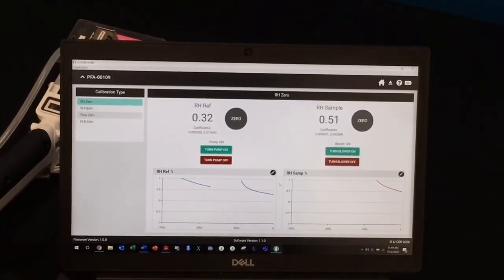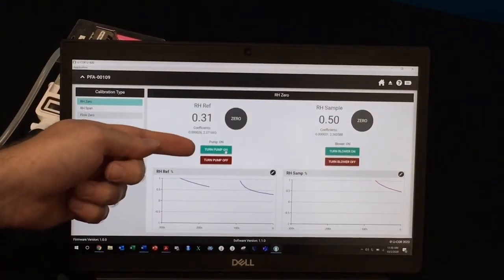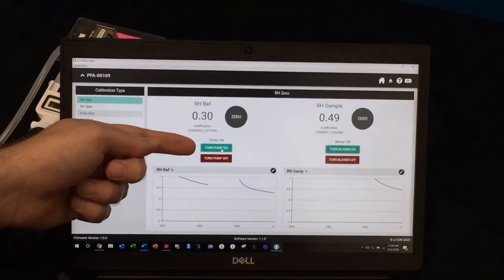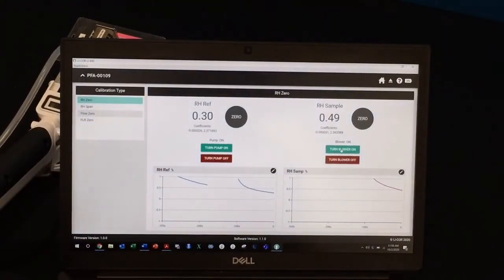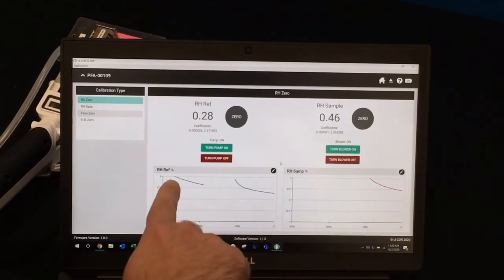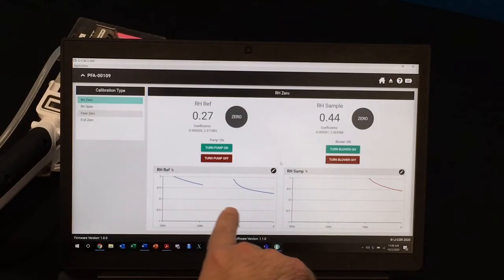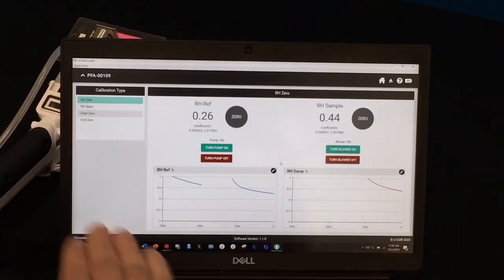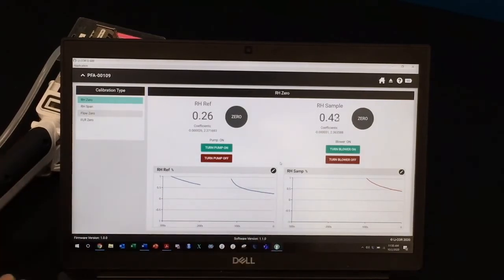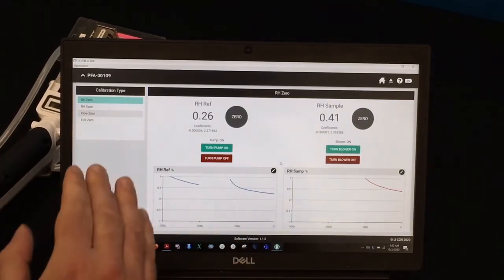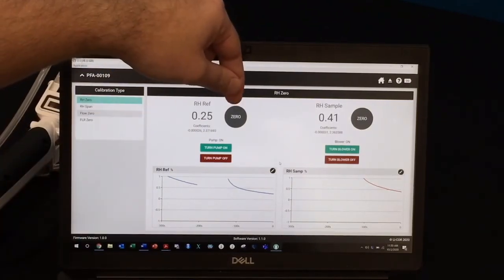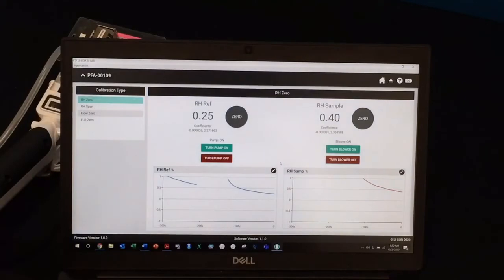Another thing you'll want to do is to ensure that the pump is on. It should be on by default, but just to make sure, you can click Turn Pump On and Turn Blower On as well. This makes sure that the air is circulating from the desiccant into the instrument. So you'll want to watch these graphs and make sure that they reach an asymptote, sort of level off. Once they're stable, which may take 30 minutes, then you will click the 0 button for both the reference and the sample. This will actually set your instrument calibration to 0 when it's seeing this dry air.